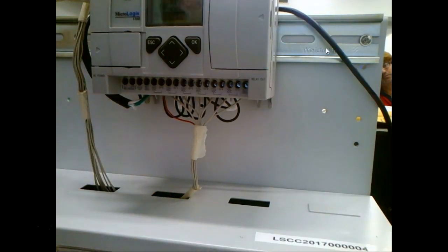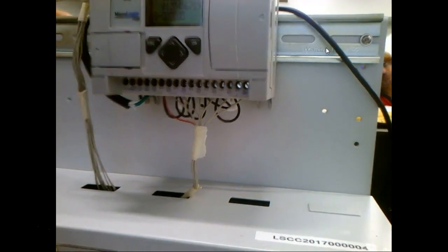So true E-stops cannot be done with software. Everybody understand that? But normally what we do is we duplicate it inside our PLC, right? You understand that? And then we actually put a true E-stop relay on the output. You can actually see this on the MicroLogix. There's a big relay right on the left-hand side of the power supply, and that's the E-stop.